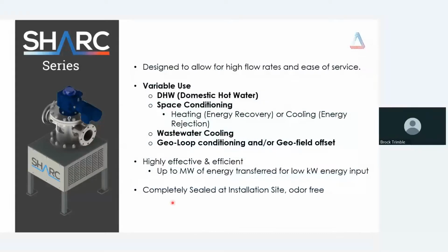So, as I mentioned, the SHARC units are designed for those high flow rates, and they're quite variable when it comes to use. So, these are the pieces of equipment that are really used for heat source and heat sink, both heating and cooling on a large scale for your projects. Using this, we are able to capture source energy that can be used for things like domestic hot water, as well as space conditioning in terms of heating. We can also provide that energy rejection, sending energy from your building into the wastewater stream to provide cooling, or we refer to that as energy rejection.